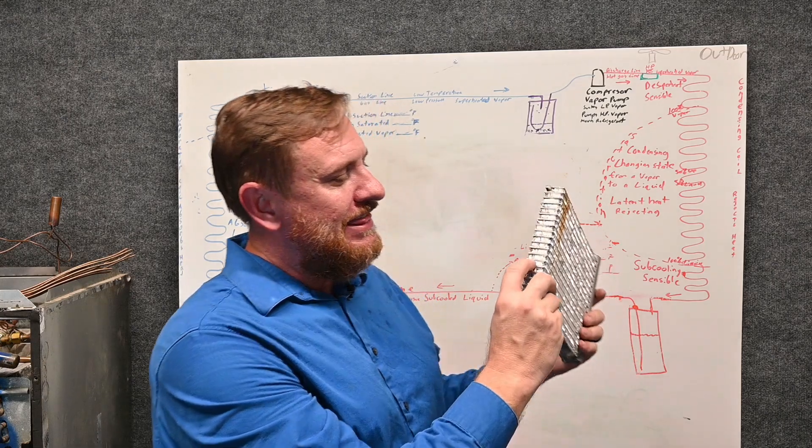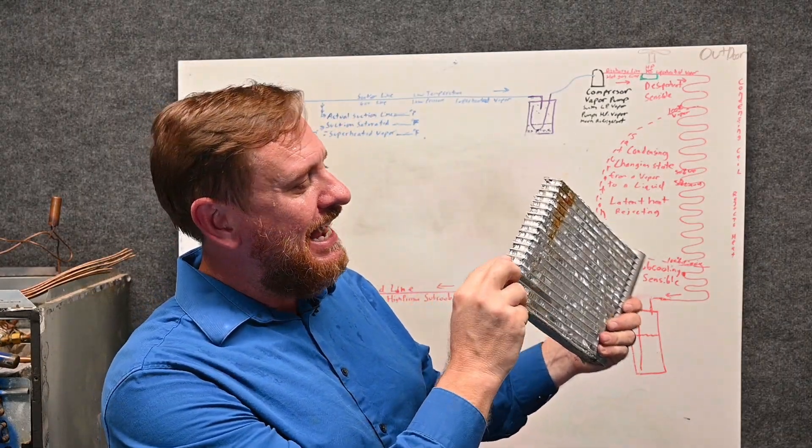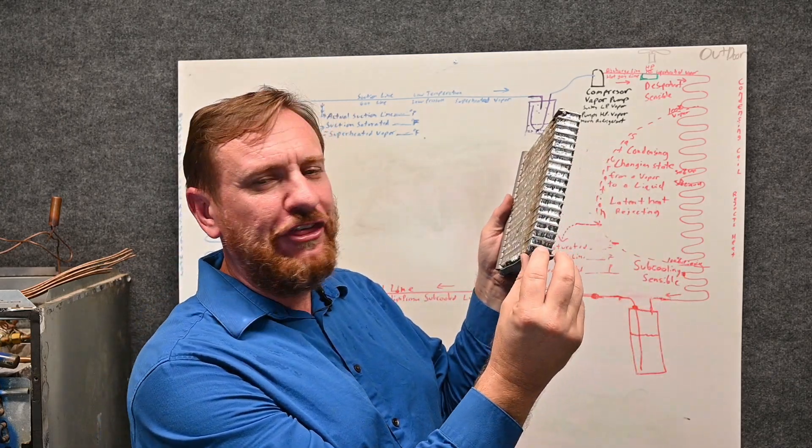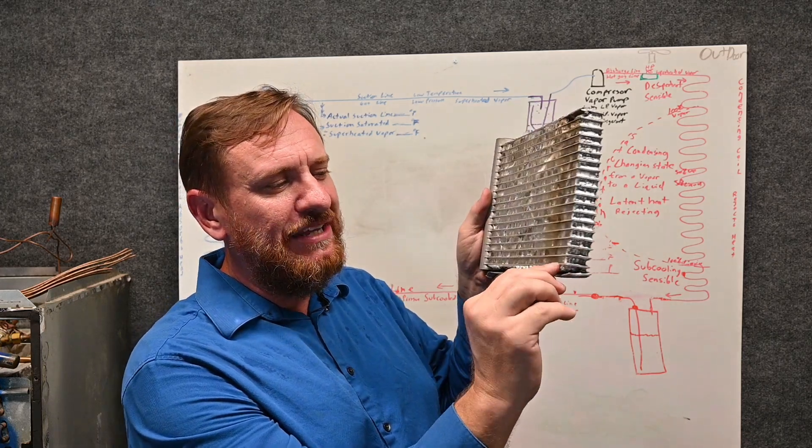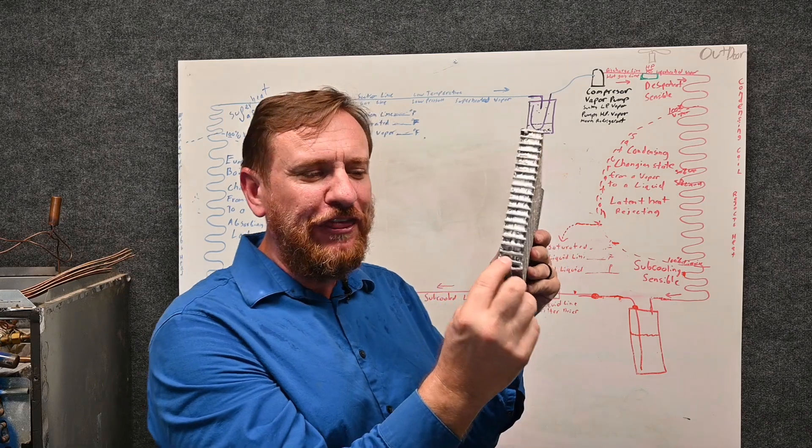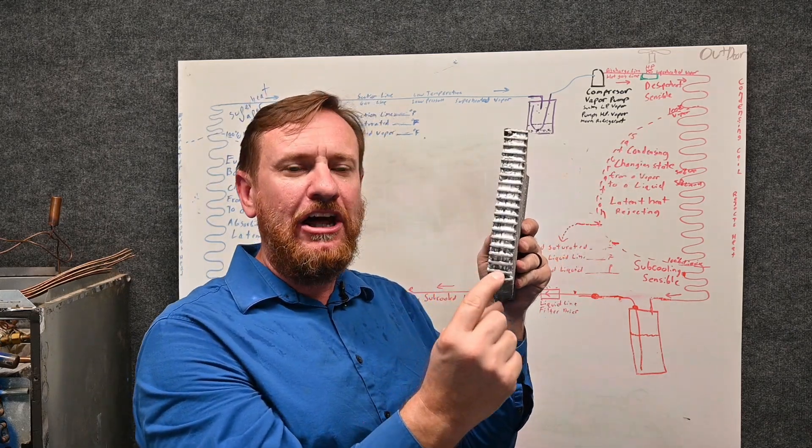But wait, it gets even smaller. These little bitty tubes right here are divided up again, and they have—let's see, this one flat channel—I'm going to count 30. So there's 30 micro-tubes in this little bitty channel. So let's call it micro-channel—a little bit, 30 individual tubes. There's a lot of refrigerant touching a lot of metal, so it's great for heat transfer. It's much better for heat transfer than this large tube.